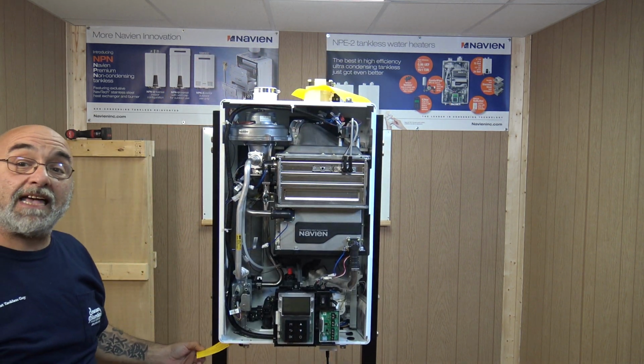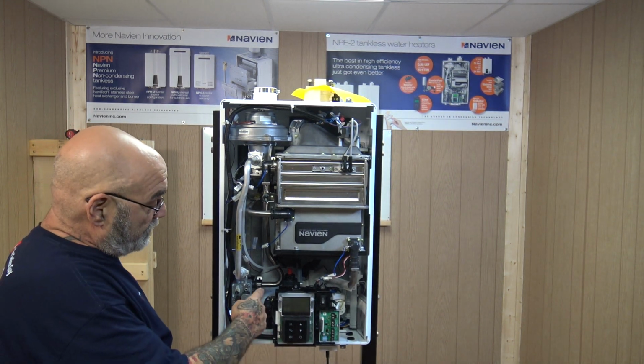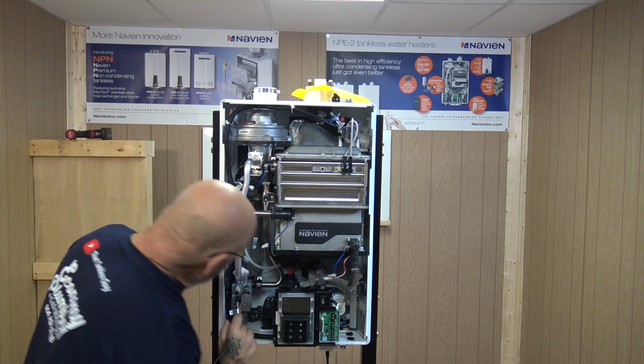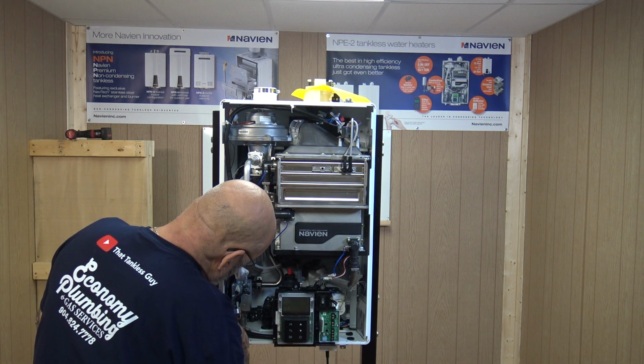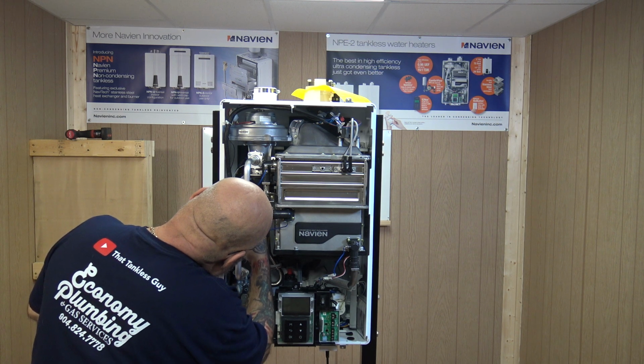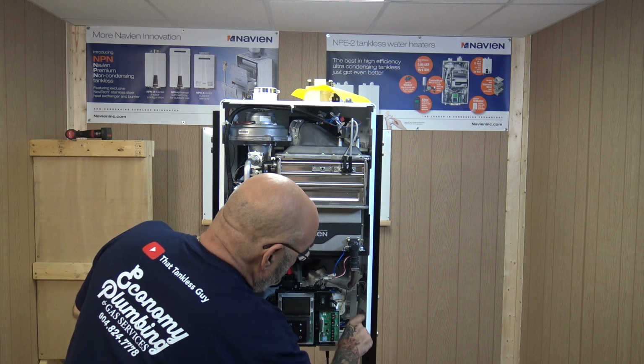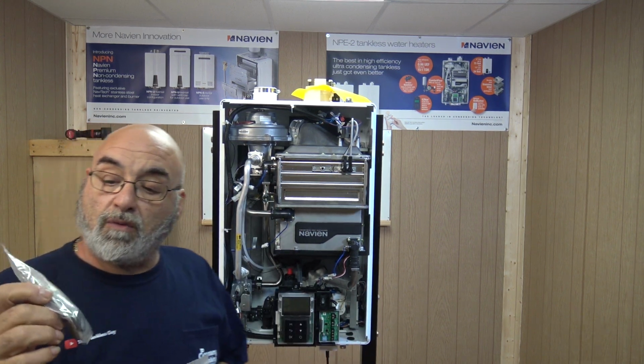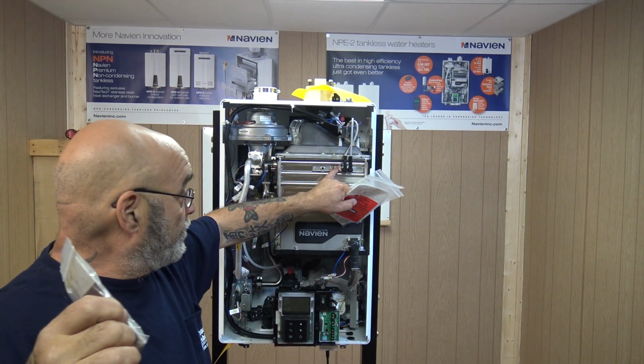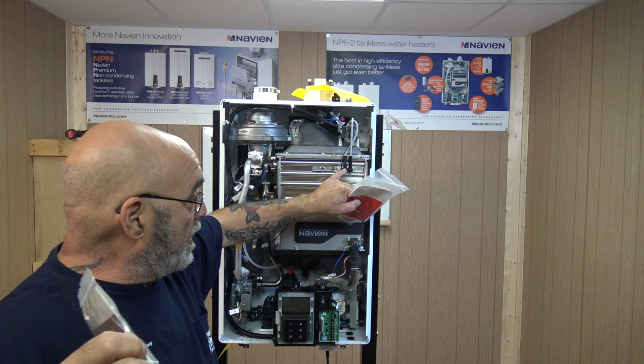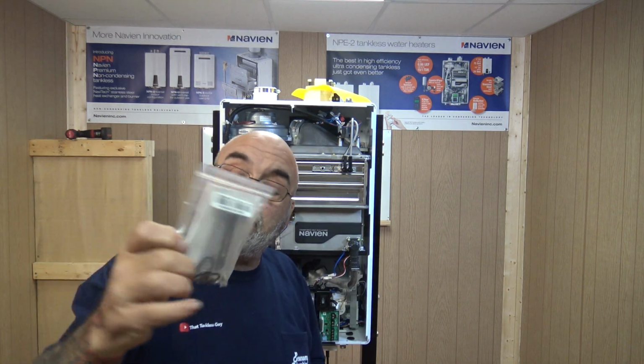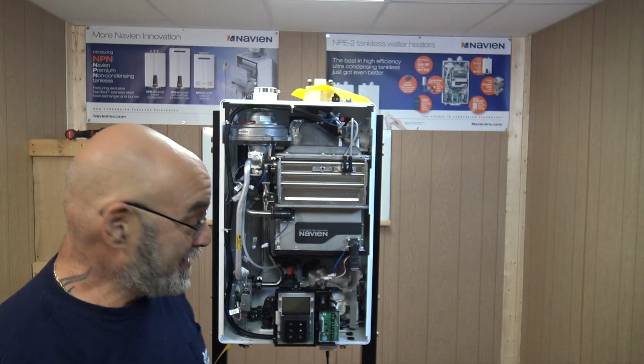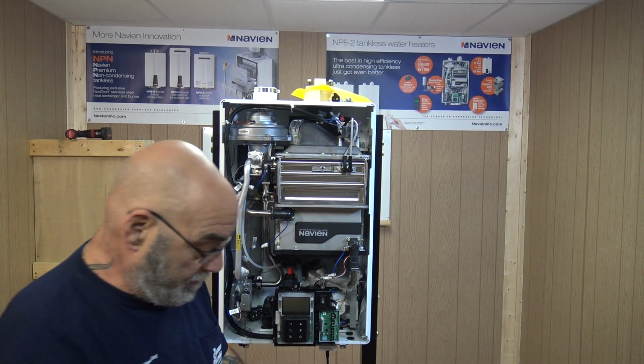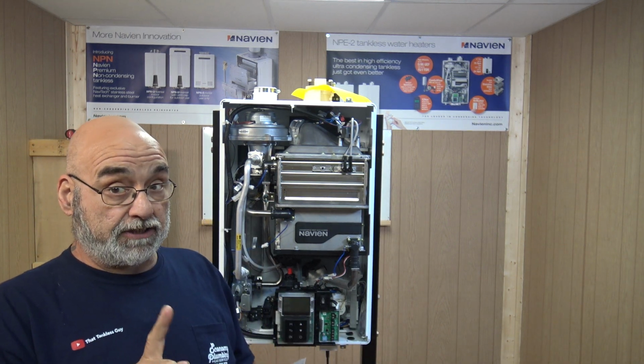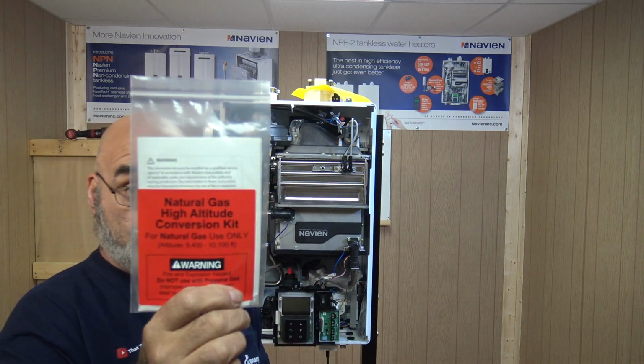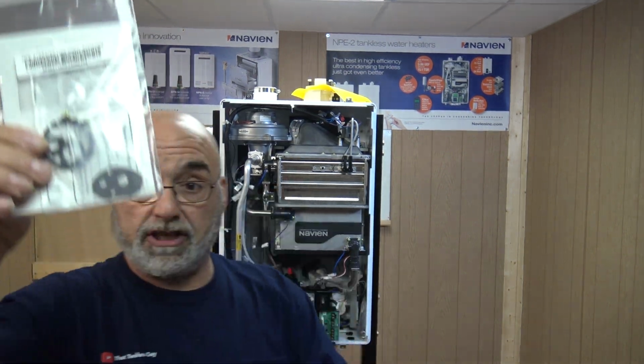There's another yellow tag here saying that it's natural gas, because when you convert this, which is right behind this plate, here is the conversion kit right here. So you get 2 conversion kits, and then you get spare parts. You get some spare parts, O-rings, sight for the opening for the igniter and flame rod. You get a fuse, and you even get some Scotch-Brite to clean the igniter and flame rod. Then you get in the kit, because remember, all of these come natural gas, a natural gas high altitude conversion kit, and that's the orifice right there.